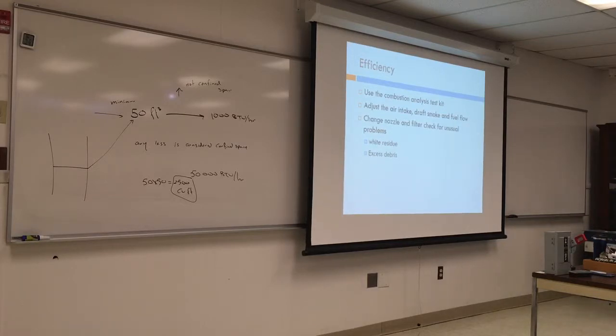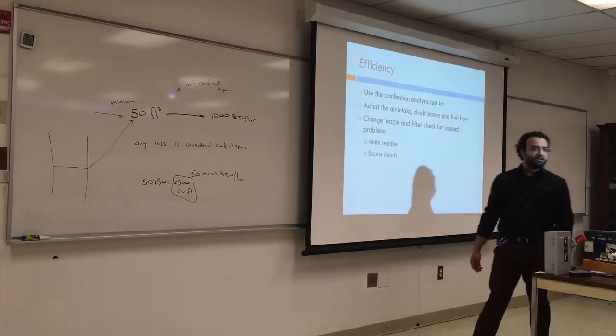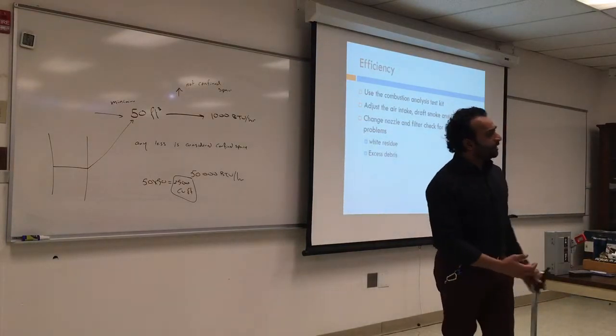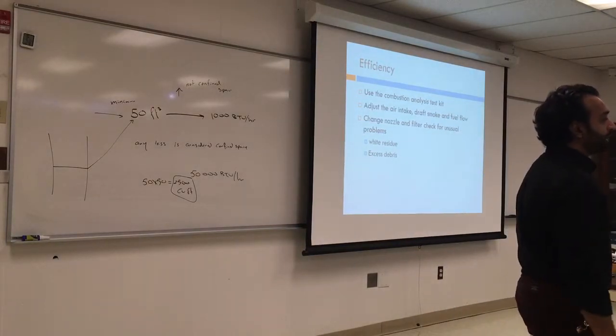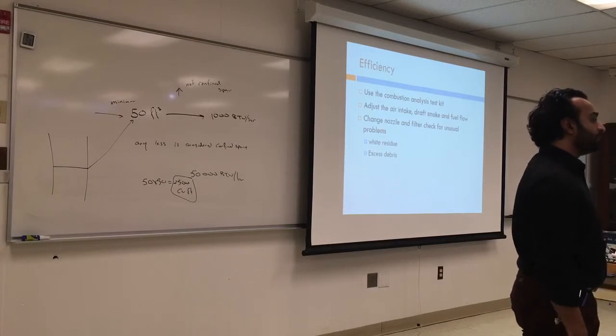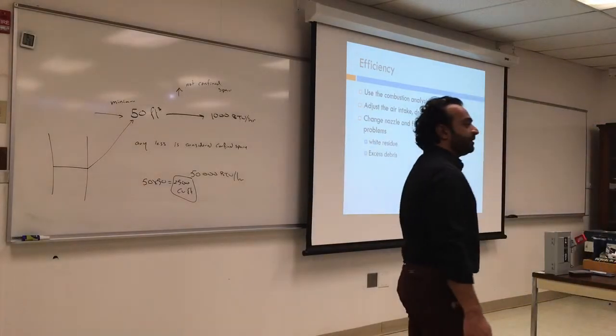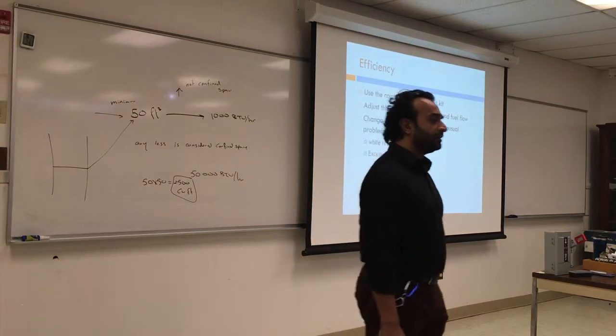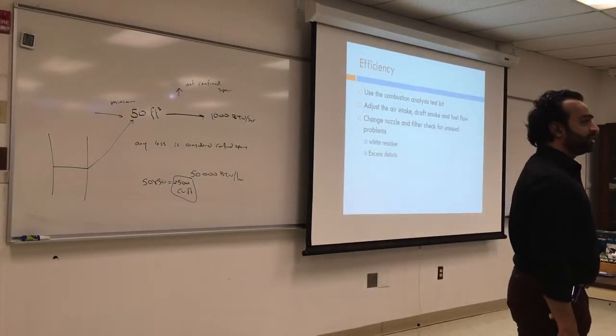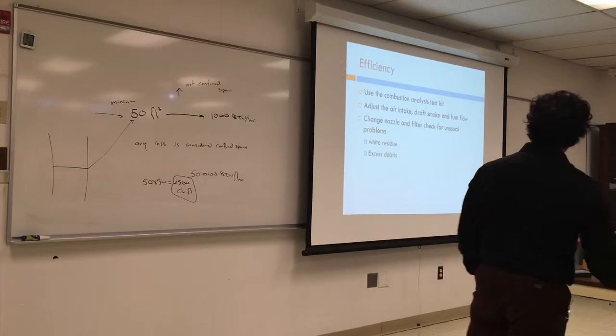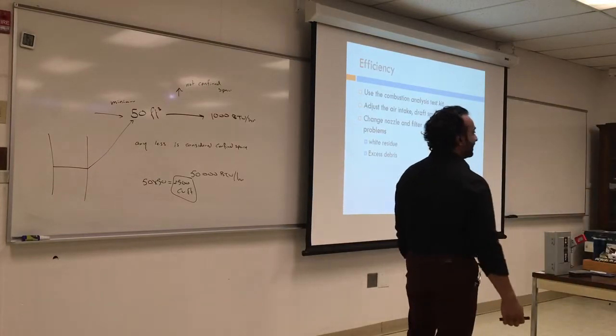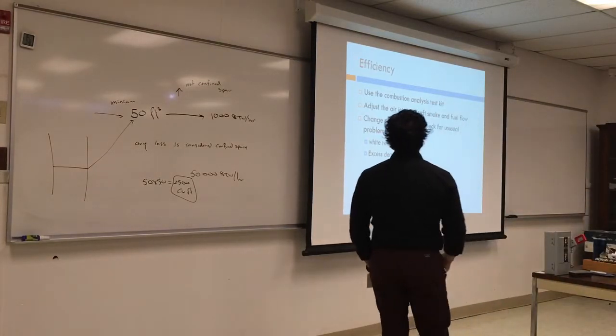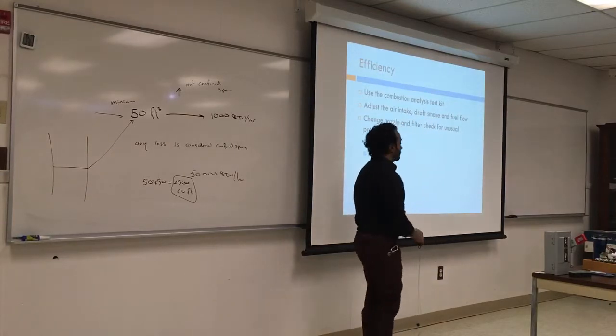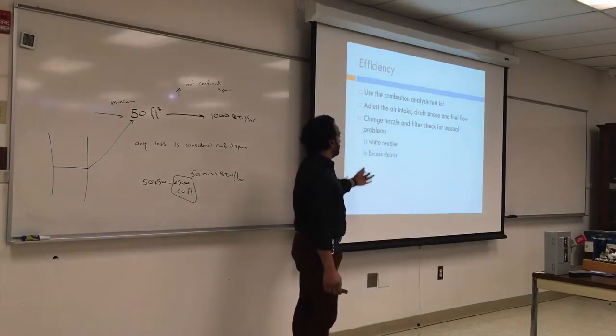These instruments are expensive and need to be calibrated every 6 months. So this is something you have if you have a company that will do the calibration, and you can replace it when you go on the job. And the mechanical kit lasts longer, requires less calibration, you can do the maintenance yourself. So they have all advantages and disadvantages. Change the nozzle and filter and check for unusual problems, white residue or excess debris.